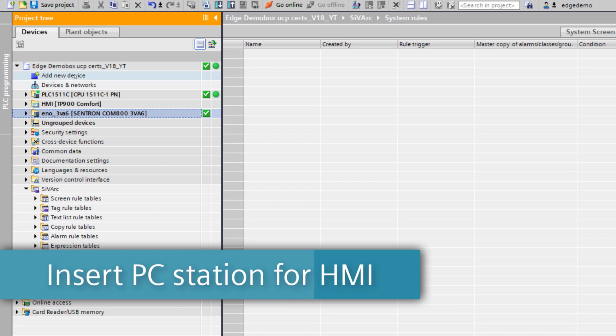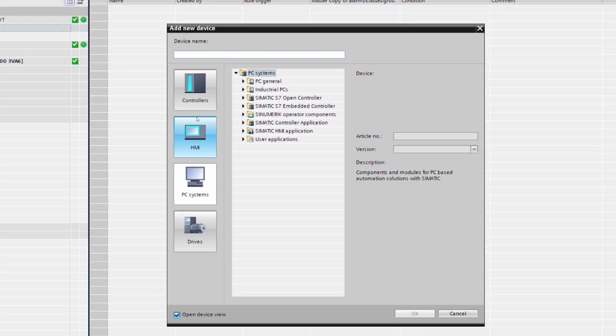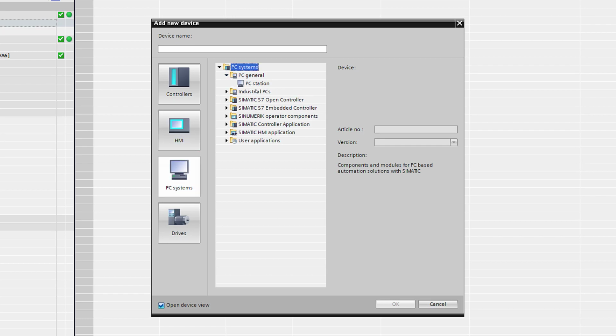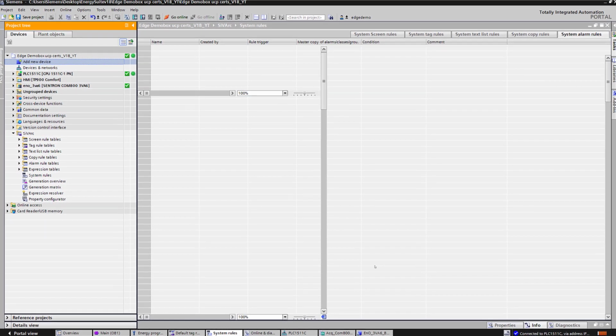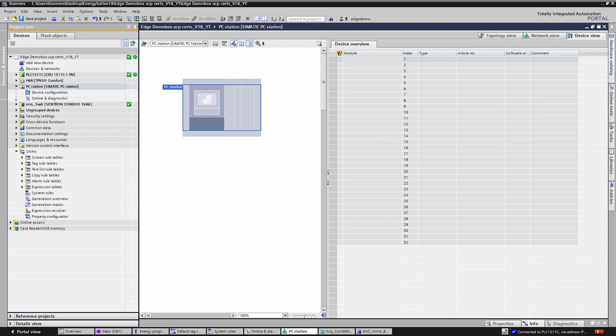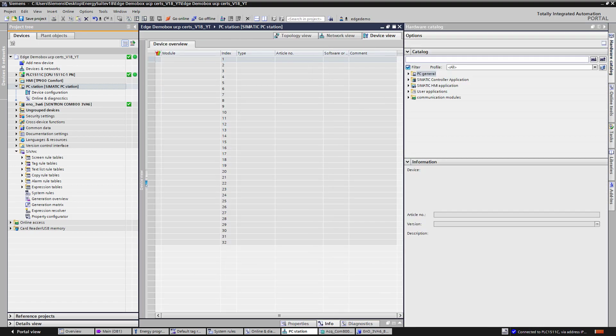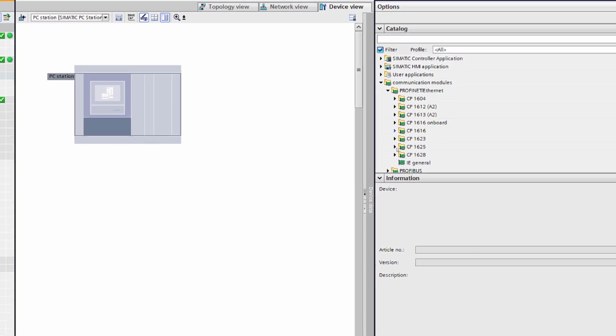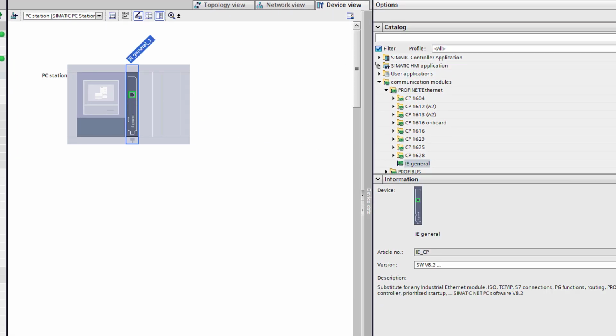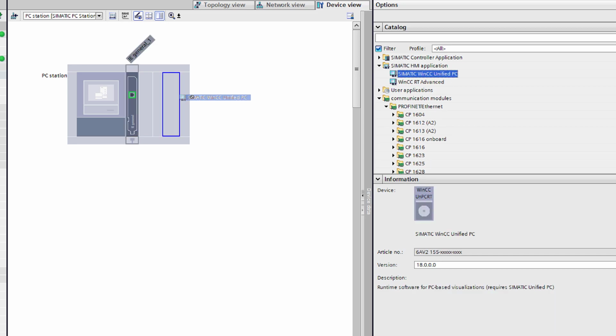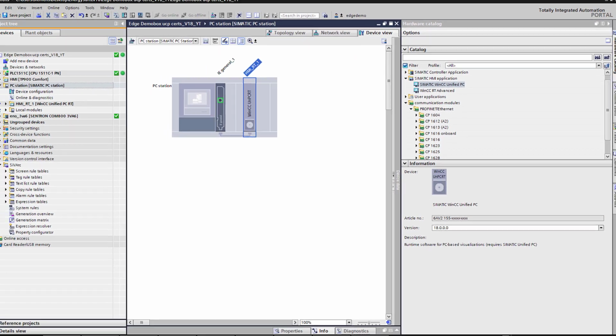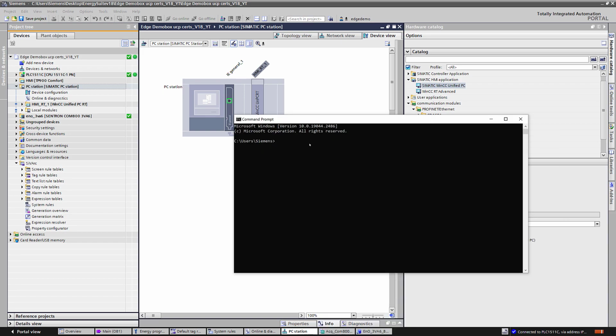So let's go ahead and generate our HMI. For this, we're going to use Unified PC Runtime, placed inside of a PC station. The hardware catalog provides us with communication modules, such as the IE General in this case, and also the SIMATIC HMI application that we're going to use, WinCC Unified PC. Now it's time to configure the IPC or PC General itself. First, we need to know the IP address. Here, the outbound IP address is .191 in my case.